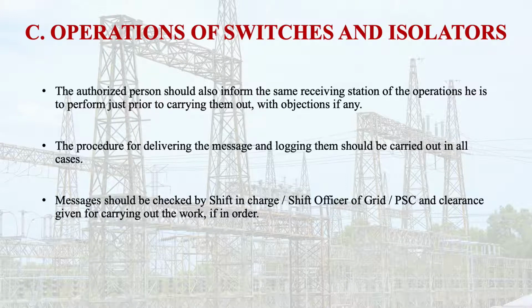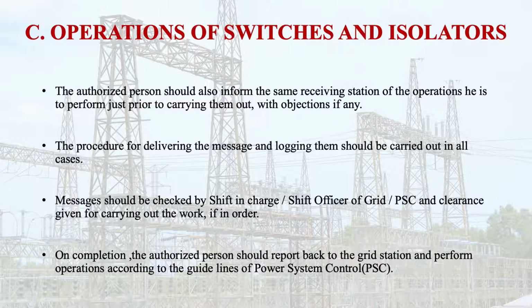So the two messages should be checked by the shift in charge or by the shift officer of the grid or power system control, and clearance given for carrying out the work if in order. On completion, the authorized person should report back to the grid station and perform operations according to the guidelines of power system control. Basically, one can work only when he has received the permit to work or the guidelines from the power system control, and these guidelines are received by the authorized person only.